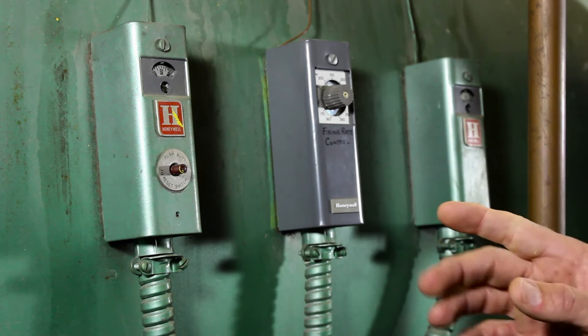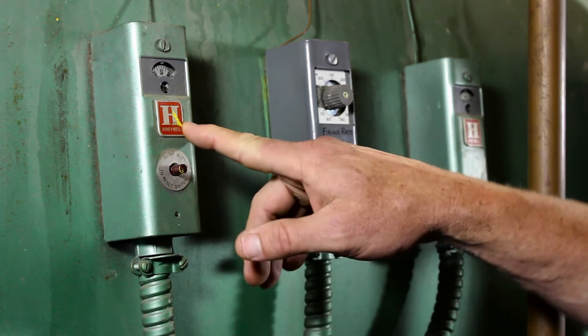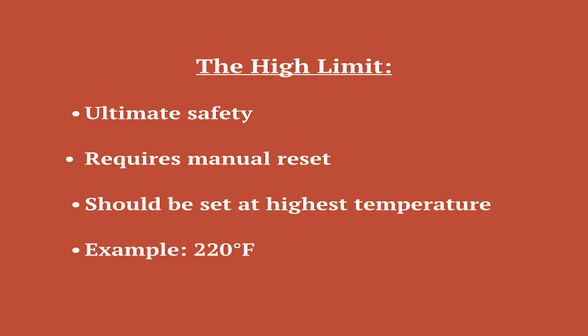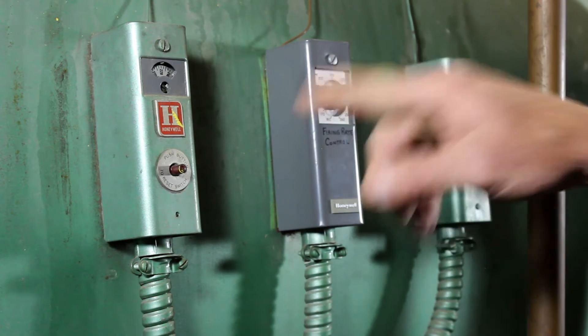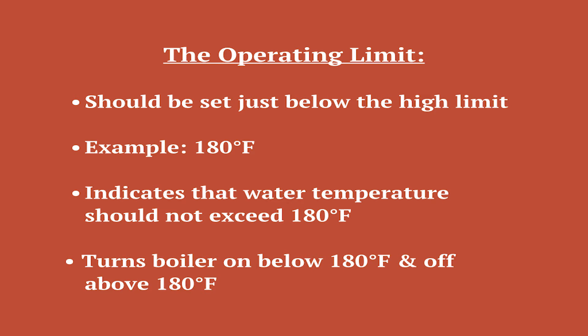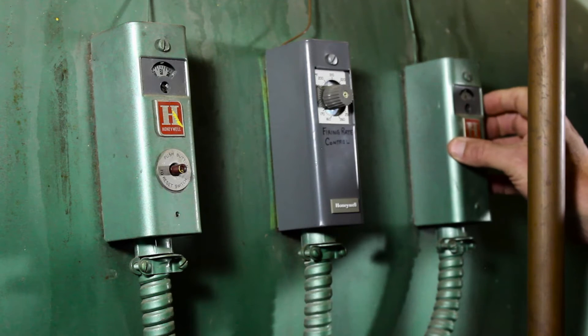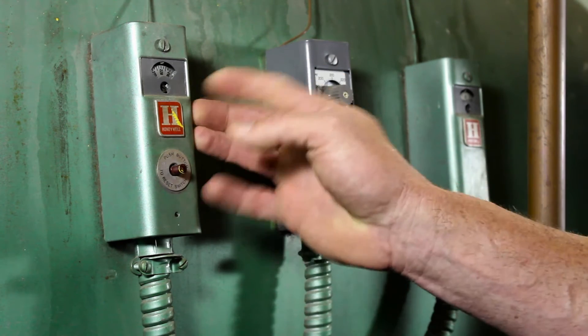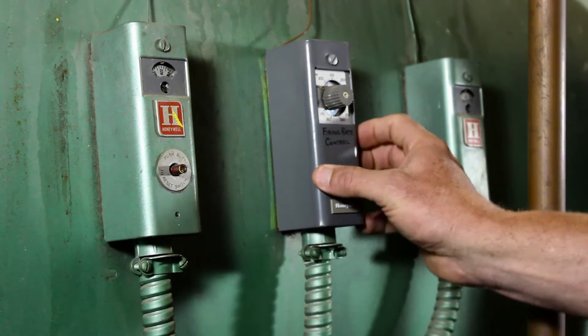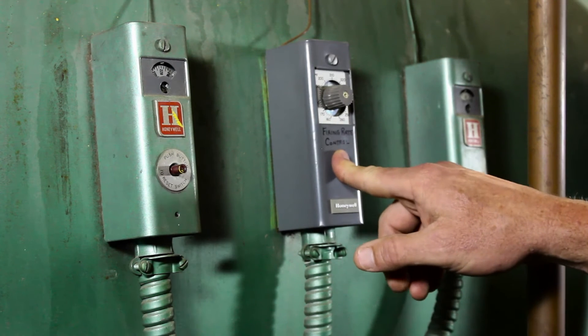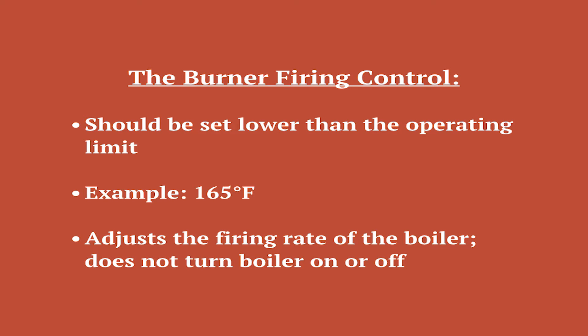The way these controllers function: your high limit is your ultimate safety, and it should be set at the highest temperature — this particular one is set at 220 degrees. Then your next safety down is your operating limit, and it should be set just below your high limit, or whatever your operating limit is going to be. This particular one is set at 180, which indicates they don't want water temperature to exceed 180 under normal circumstances. If this controller fails and the water temperature continues to rise and gets to 220, then this manual reset controller will trip it off. Your last controller is your modulating controller, which is your firing rate, and it should be set less than your operating limit.